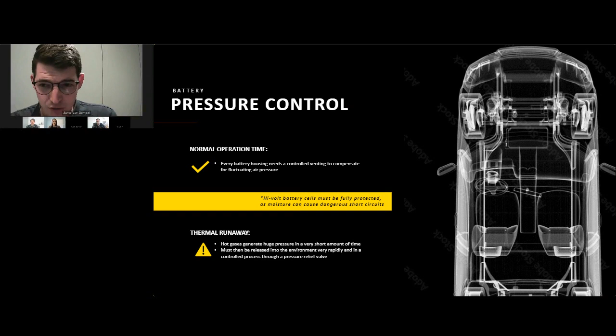As Matthias explained well, over time, processes like charging the battery, discharging it, overcharging or over-discharging it, as well as aging and corrosion, will lead to the creation of gases inside the battery system. In the worst case this might even lead to a thermal incident or thermal propagation, where we need to rapidly evacuate a lot of gases. So these are the first type of pressures we need to manage: those in case of a thermal runaway, an emergency situation.